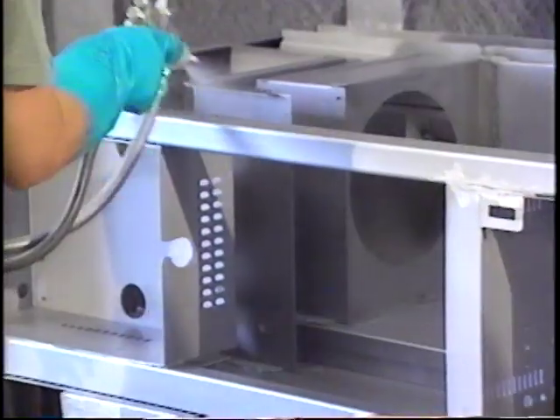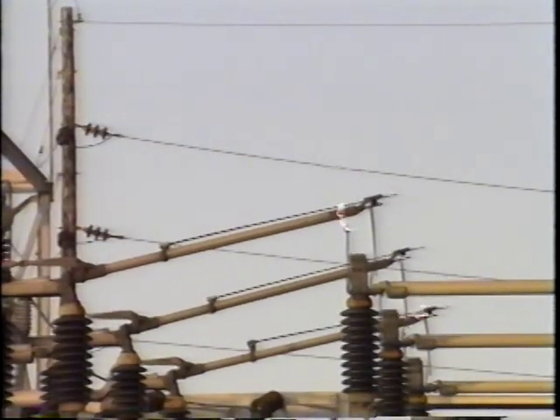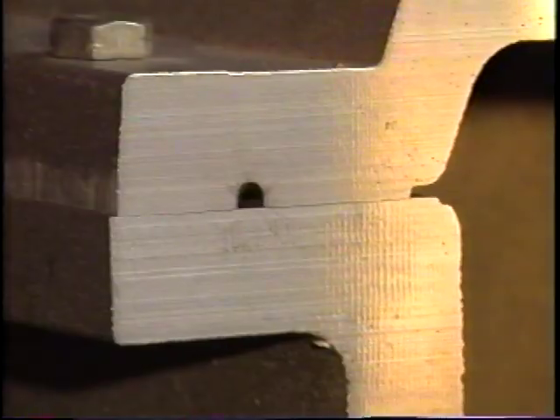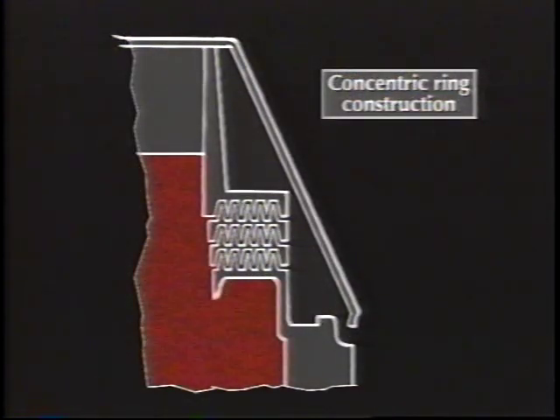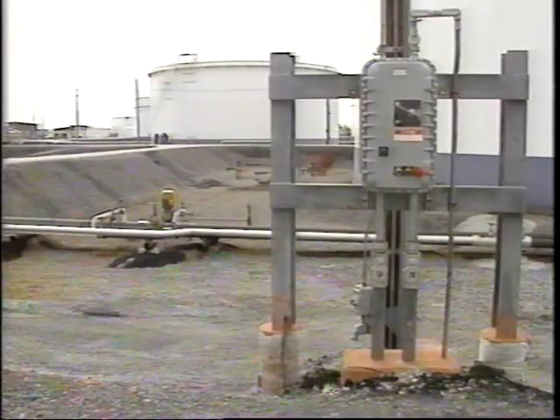There are thousands of places where processing operations can create areas with hazardous atmospheres. If you have the wrong type of electrical system in a hazardous area, the smallest spark can cause a fire or a devastating explosion. To be safe, you must use special electrical equipment that's designed for use in hazardous areas. The design of this special equipment works to contain an explosion and then slowly vent cooled gases to the outside atmosphere, which prevents the ignition of the external atmospheres.